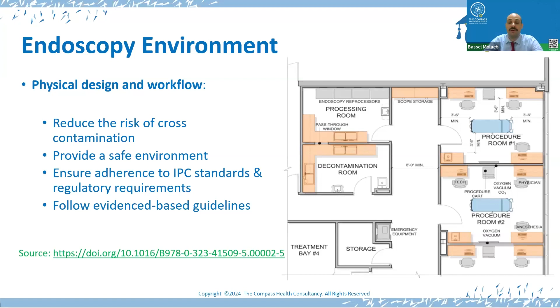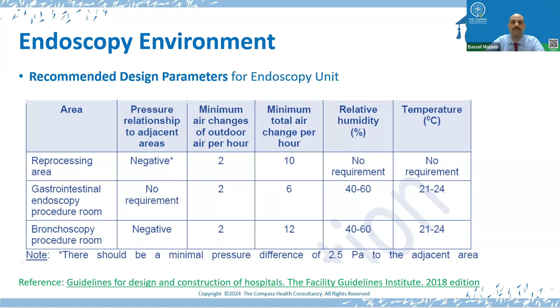Each area within the endoscopy unit should have a designated flow for the safe physical movement of dirty scopes that do not cross-contaminate with the clean scopes, which will come out of the cleaning process and go to the storage area. This table represents the design parameters, and as you can see, we need to ensure that in the reprocessing area we have negative pressure. The minimum air changes per hour should be 10. For the procedure room, there is no requirement to have negative pressure; it's equal pressure. And a bronchoscopy procedure room, which is considered an airborne isolation room, should have negative pressure with 12 air changes per hour.